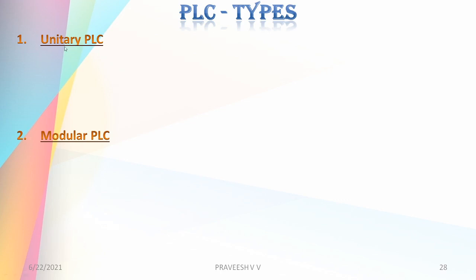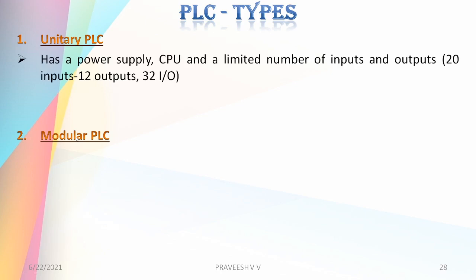Basically we have unitary PLCs and modular PLCs. In unitary PLCs, the input and output ports are fixed and are included along with the PLC, embedded with the processor. It has a power supply, CPU, and a limited number of inputs and outputs — generally 20 inputs and 12 outputs in a 32 IO unitary PLC.